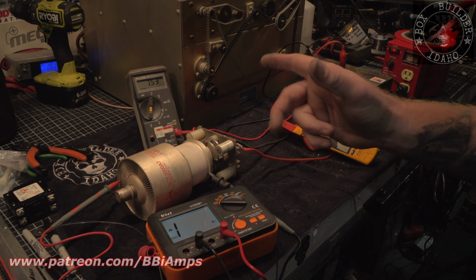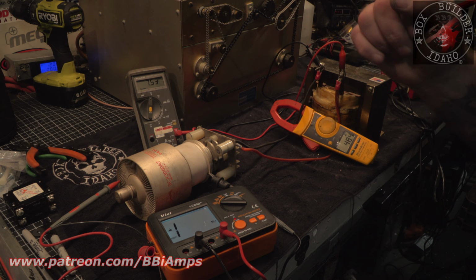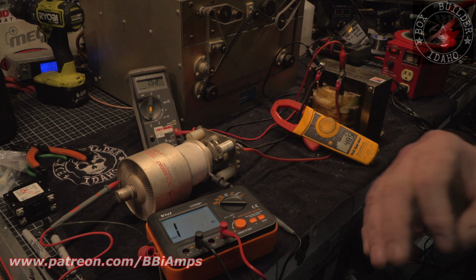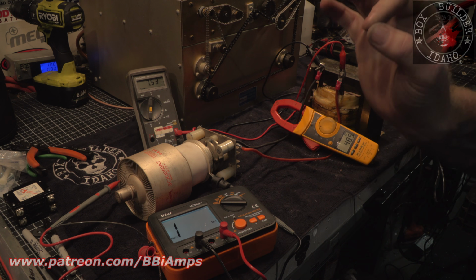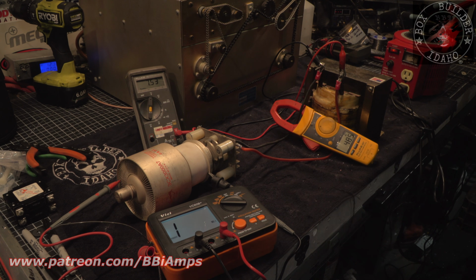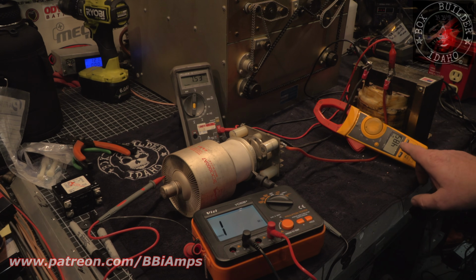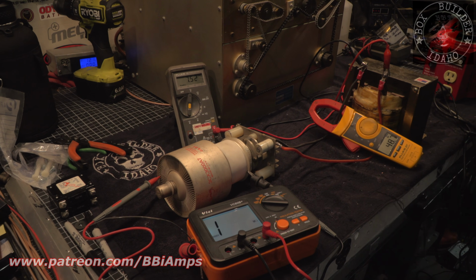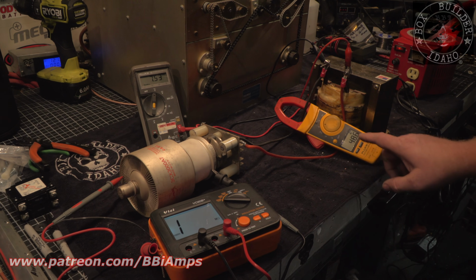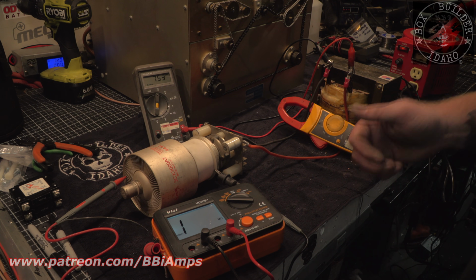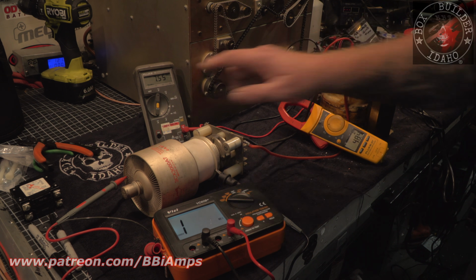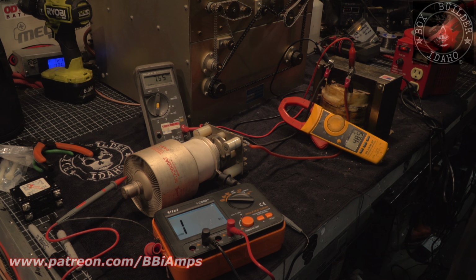So we know that there's no hard shorts between the anode and the ground ring, which makes me very, very happy. And this is actually dropping off a little bit as the tube is warming up. We can see our voltage is starting to climb up a little bit as the load's coming off. So we'll go ahead and back this down just a hair.